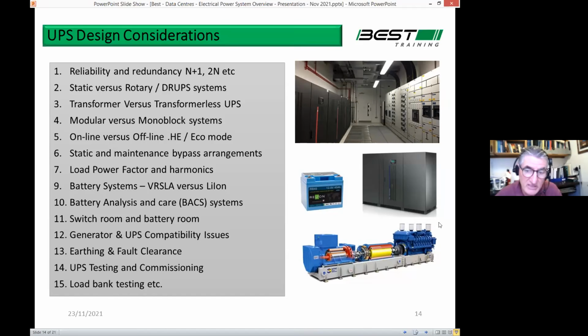to allow the diesel engine to start up. Normally the motor generator part, I should have explained that at the start, is running away and driving this flywheel. It's spinning around, and the power is going into the servers in the normal way. When the power fails, the flywheel continues to run. It continues to drive the motor generator set, which now turns into a generator, and the generator then delivers the power to the load. So the flywheel is about 10 to 15 seconds of energy storage. In the meanwhile, the diesel generator starts up, a clutch mechanism closes here and links the diesel set back onto the flywheel, back onto the alternator, and Bob's your uncle. And that's how that works.